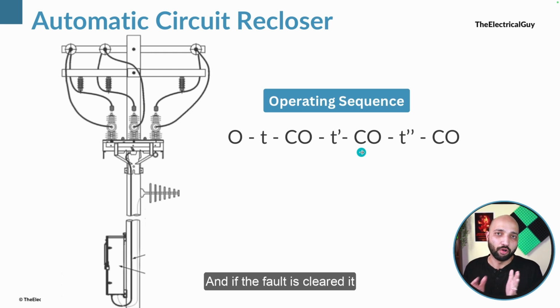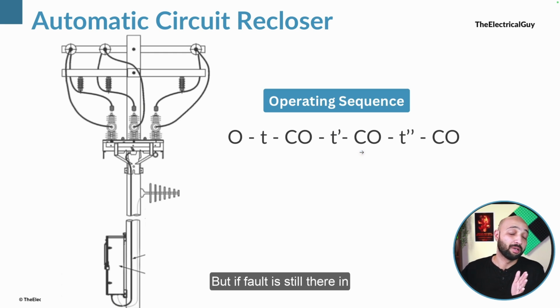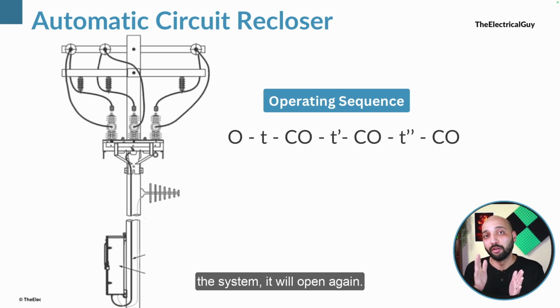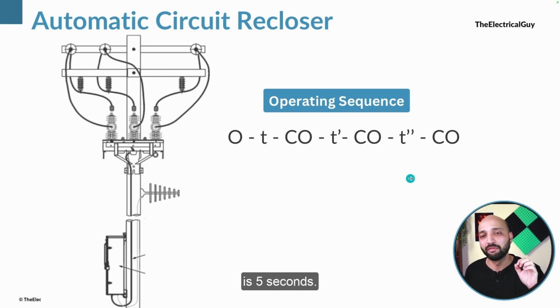And if the fault is cleared, it will remain in the closed condition. But if the fault is still there in the system, it will open again. The moment it opens, it will again wait for some time. Now this time again, it will wait for some more time. This time is generally 5 seconds.